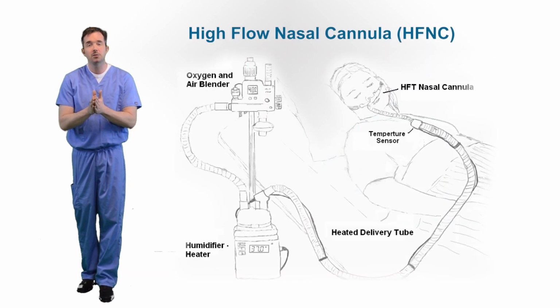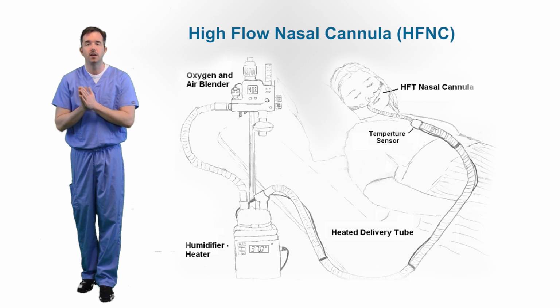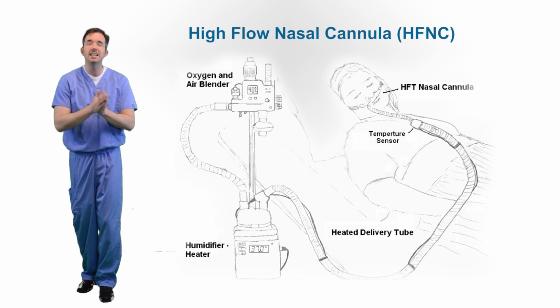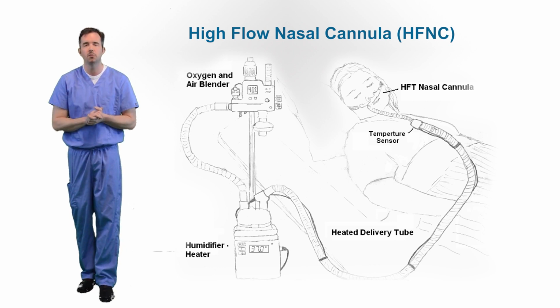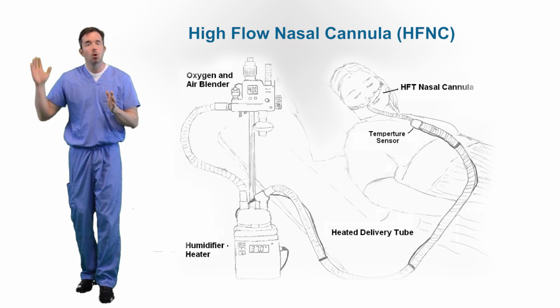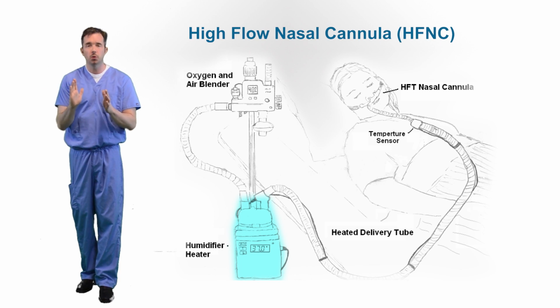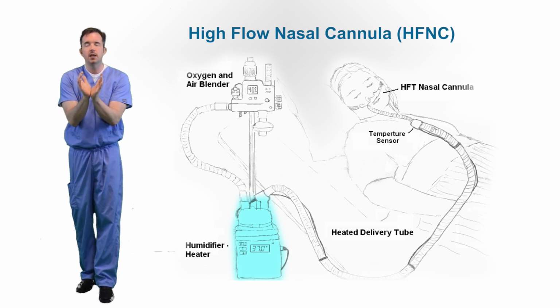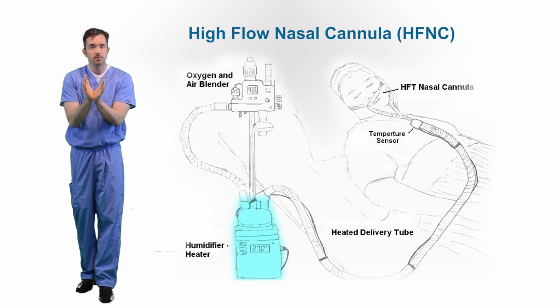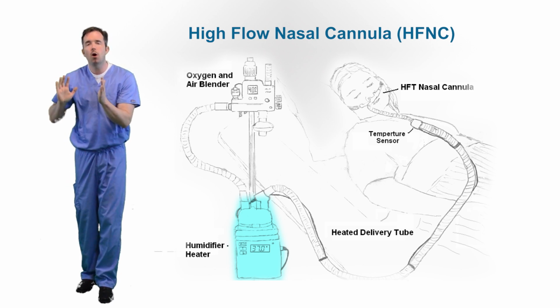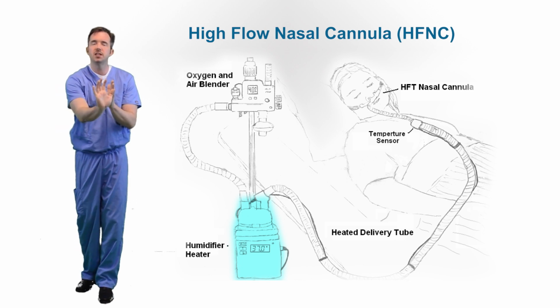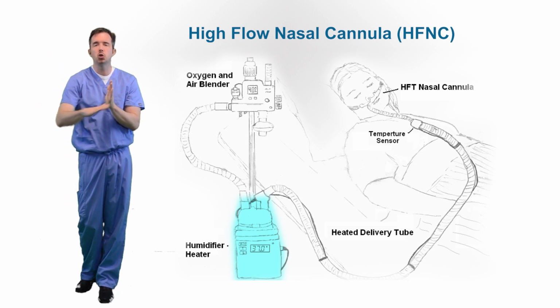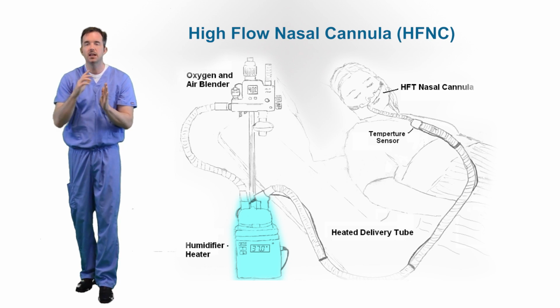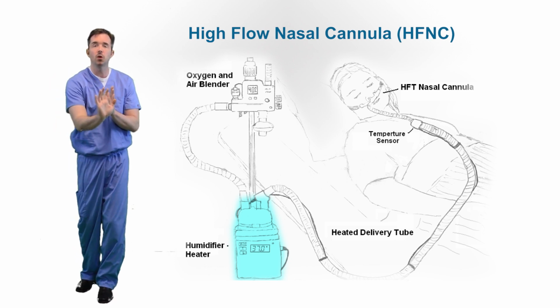All right, now to move on to the high-flow nasal cannula. Sometimes you even call this the heated high-flow nasal cannula, depending on the manufacturer. Here's how these work. These are a bit different in that while oxygen does come from the wall of the room, it goes into a machine that infuses humidity, which is great to prevent nosebleeds and increase patient tolerance, but it also increases flow, such that now the oxygen going from the tubing of the machine to the patient's face can be pumped in at a higher flow rate.